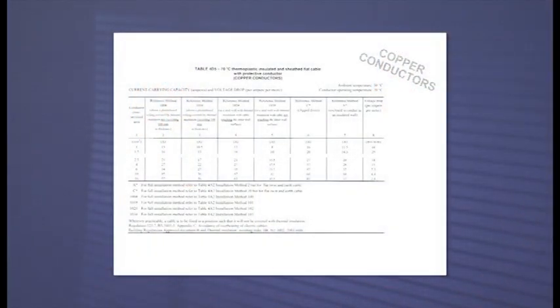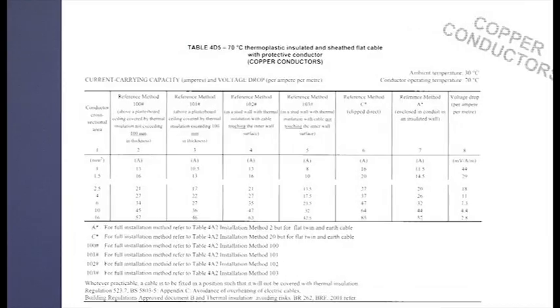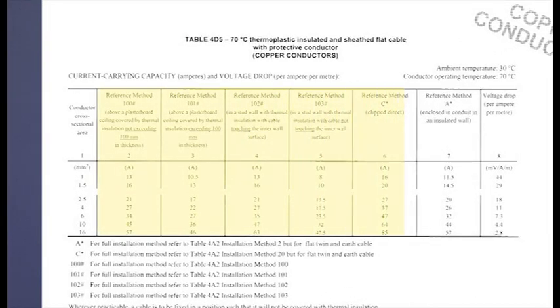For example, if I look at table 4D5, which is the current carrying capacity for twin and earth cables, you'll see that there's 6 reference methods. Reference methods 100 to 103 are to do with thermal insulation, depending on the thickness of the thermal insulation. And reference method C is if the cable is fixed direct. Now it's these reference methods that will go in the box on the circuit details.